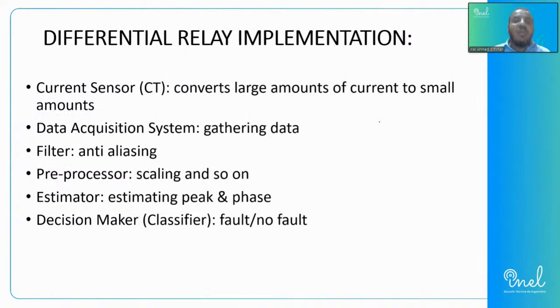And from here, we should confirm how to implement a differential relay. To implement a differential relay on a certain protected zone or on a transformer, there are certain items and components we should confirm. There is the current sensor or current transformer. We have a data acquisition system to collect the currents, process them, and compare.